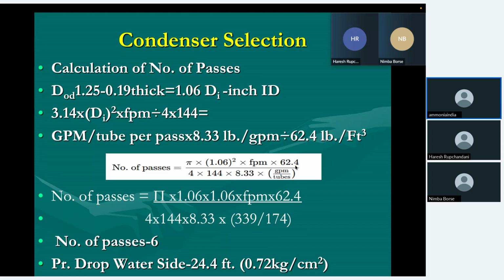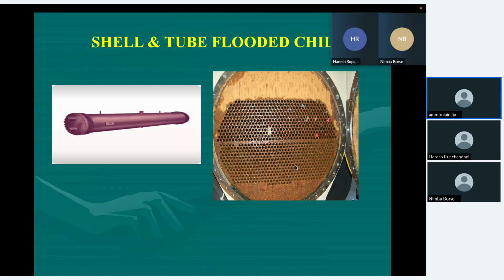So the pressure drop on the water side, from the catalog, you will find will be around 0.7 kg per centimeter square, which is moderate, and therefore we decide that our calculations are correct, our velocity is correct, and our selection is correct. So now we go to the next vessel, which is the shell and tube flooded chiller.